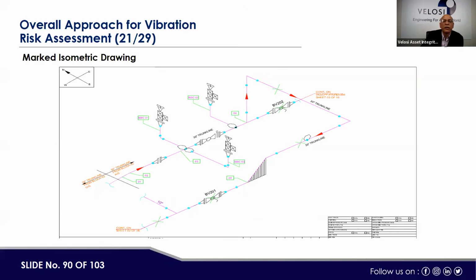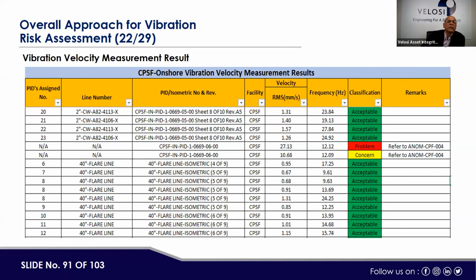Here is a marked isometric drawing. Here, you see the same locations, which we call TML or CML locations, 1, 2, 3, 4, 10, 8. So these locations we marked on the isometric, and then measurements were taken. For all these locations, the P&ID, assigned number, line number, facility, velocity measurement, and acceptable or not acceptable are listed. So here we can say, refer to anomaly CPF04, again a problem concern, because here the measurement is 27 and the RMS is 10.68 mm per second. All others were considered acceptable.